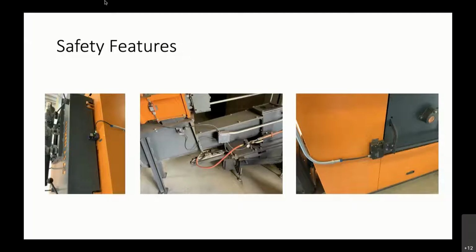And the same with that burn back gate. In the central picture there, it's a little bit hard to discern, but there's a safety valve. So if you have any kind of temperature rise in the back end on the stoker side of the boiler, then in fact you have a safety valve that can not only douse it, but it can close it with a pneumatic valve. And so the pneumatic valve then activates, closes out the fuel, and everything is safe, so it cannot burn back into the store chamber.